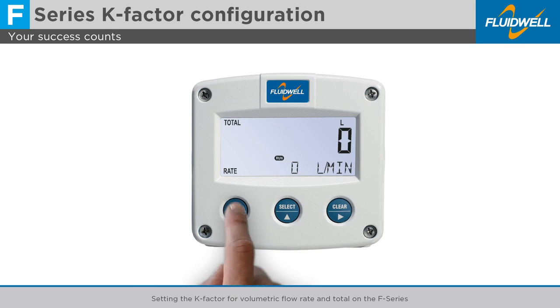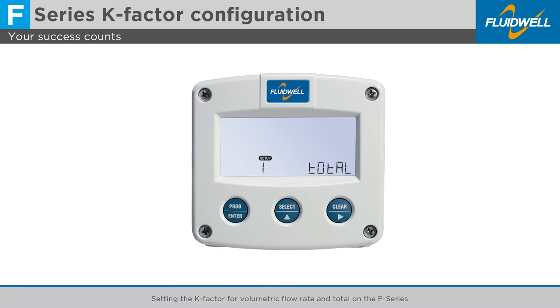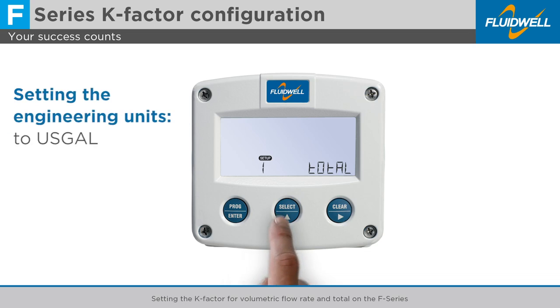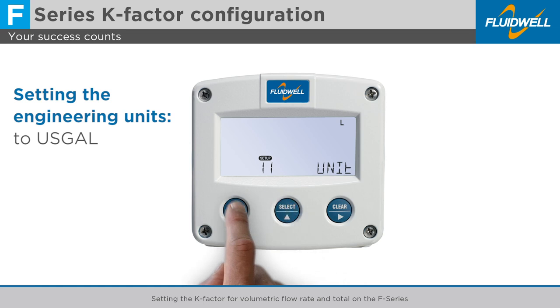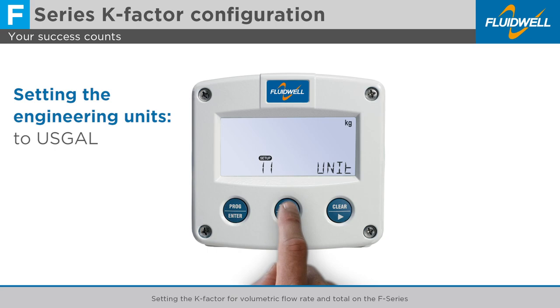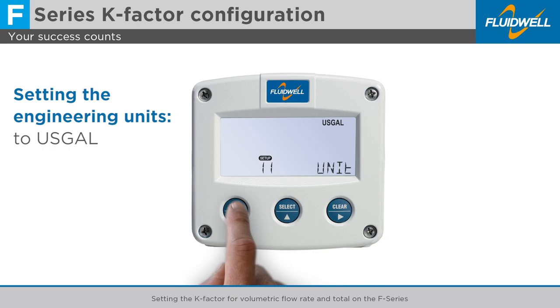Hold the Program button for 7 seconds. Menu 1 Total appears. You can use the Clear and Select buttons to navigate through the menu. Use Select to go to Menu 11 Unit. Select the engineering units for Total. Press Prog to change this setting. Select US Gal. Press Prog to store this setting.